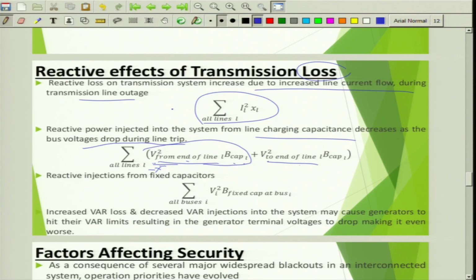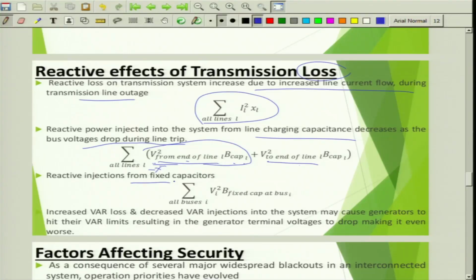On one side there is an increase in line loss because one line is being taken out, and in the remaining lines there is increased line loss. Because of the absence of charging capacitance, the capacitance which would have supported reactive power has been taken off. And then reactive injection from fixed capacitors: there are also fixed capacitors present within the line, and that is also not present because the line itself is not present. So that is also not able to meet the expectation. On one side there is an increase in reactive power flow through one line, because of which loss is increasing, and on the other side there is a lack of reactive power support because of the absence of charging capacitance and the shunt capacitors present in the system.